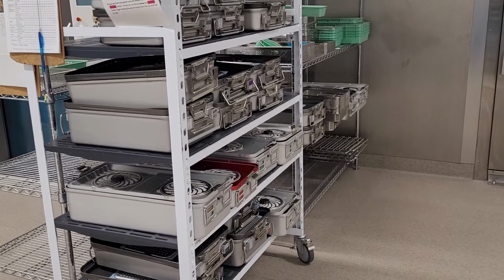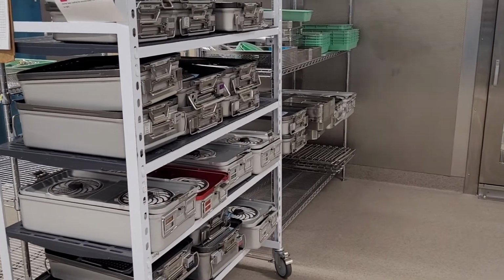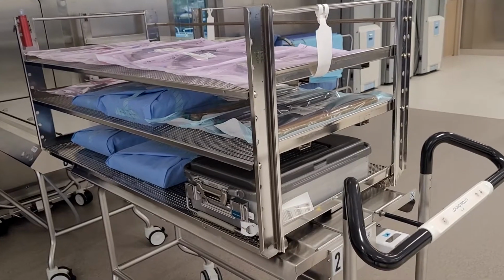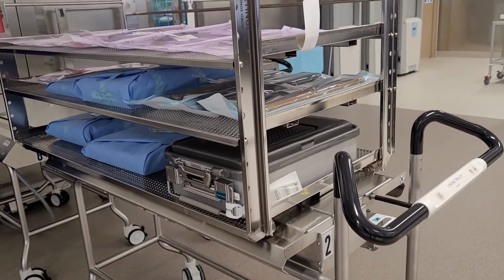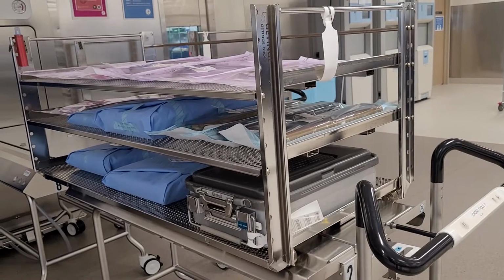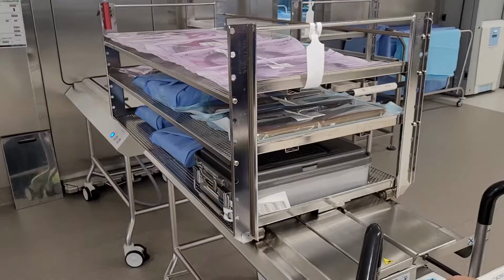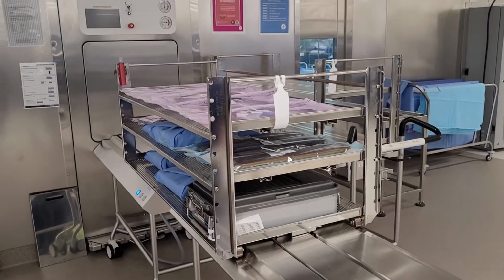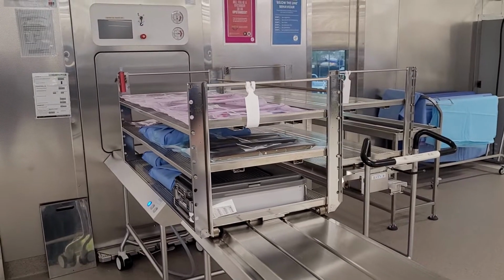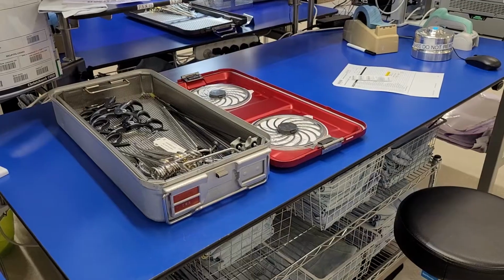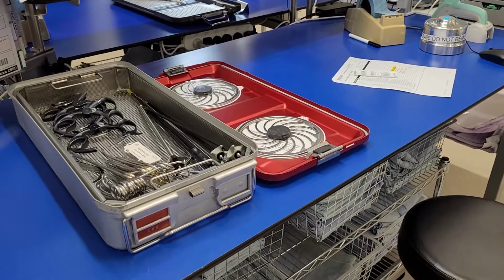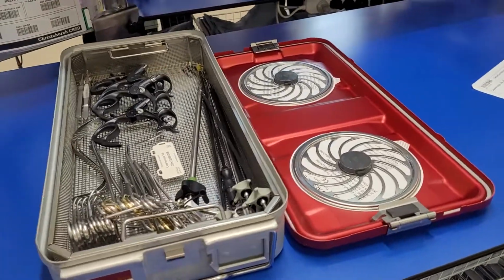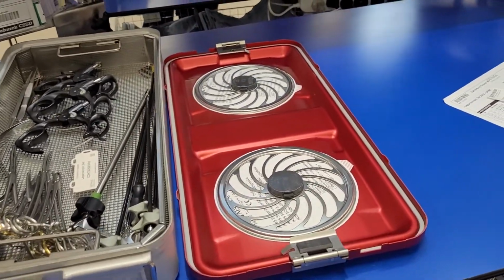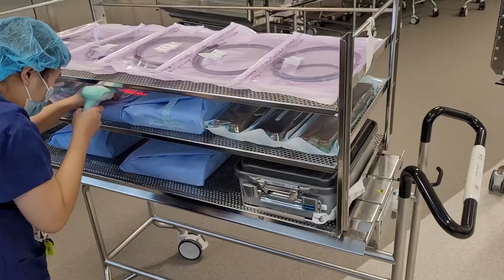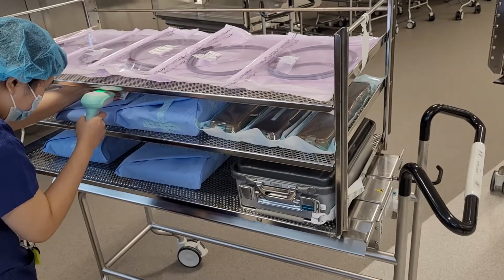Rigid containers are mostly used for steam sterilization. Sterilizing takes place after cleaning. It involves exposing items to steam, hot air, or sterilizing agents to rid items of remaining living microorganisms. These sterile items are then used in surgical procedures. The packaging material, whether it is used as an inner or outer wrap, must be compatible with the items being packed and the sterilizer being used.